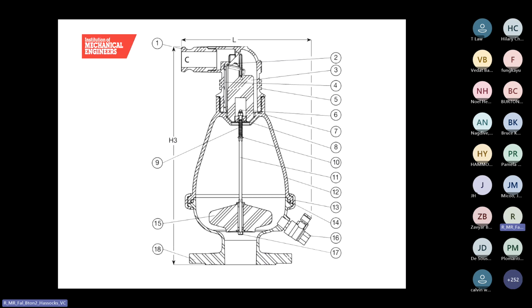Here's a diagram of a dual orifice air valve for a wastewater application. You'll see at the bottom there's a flange connection which connects to the rising main. And above that is a large chamber which has a float in it on a spindle. As large quantities of air pass through the valve, they exit through the large orifice. But as the air escapes and the water level rises, the float at the bottom gets pushed up and it closes the large orifice. The small orifice still remains open to allow smaller pockets of air to escape.